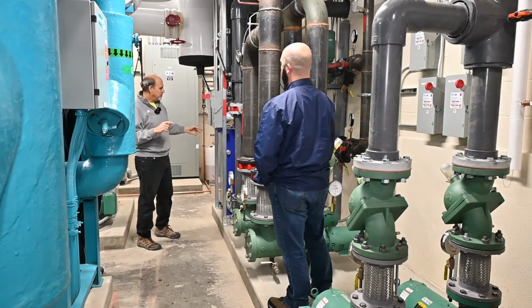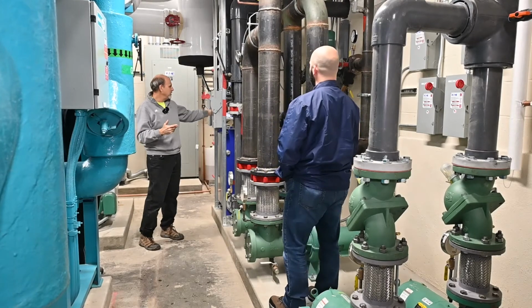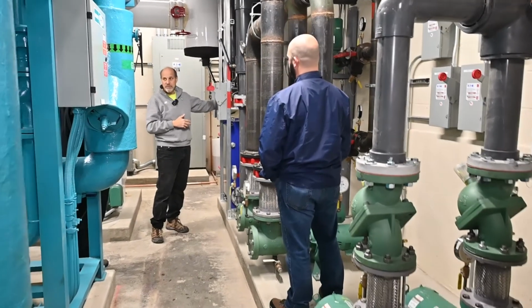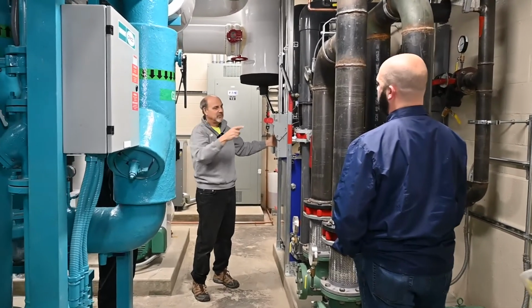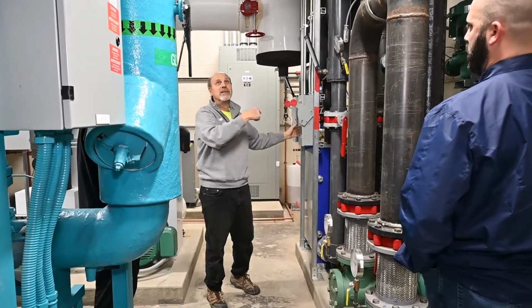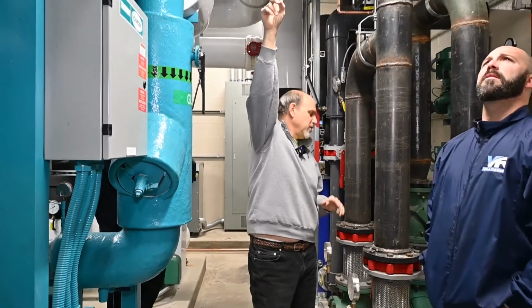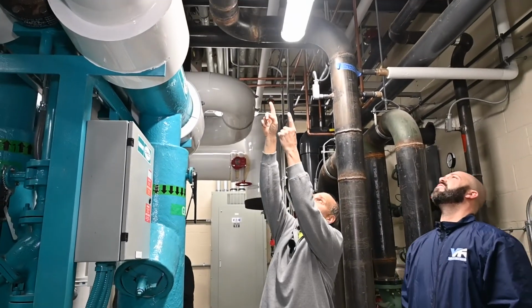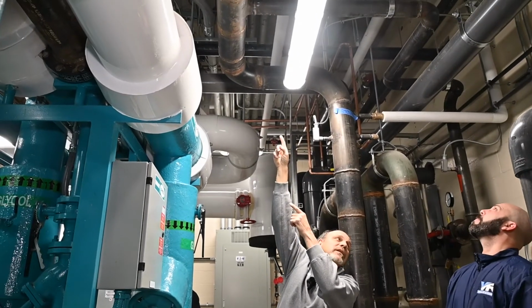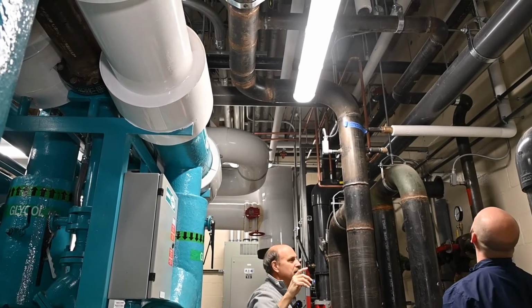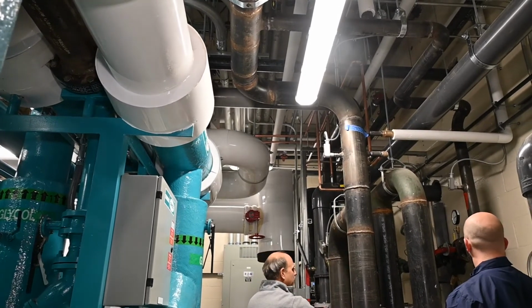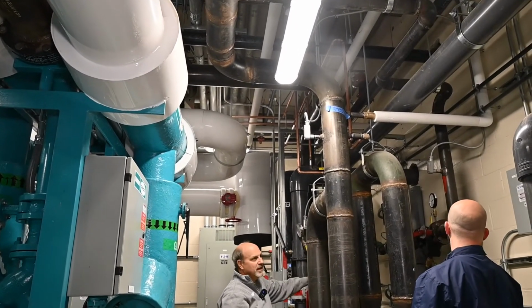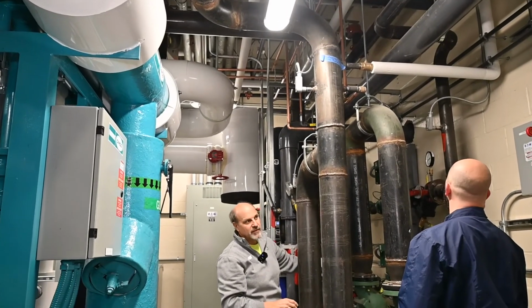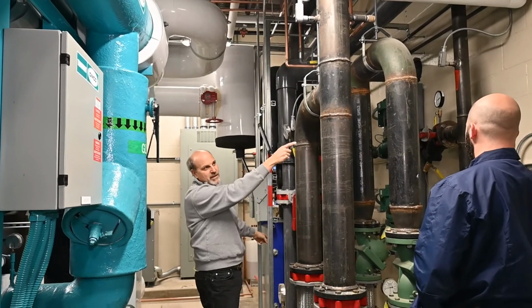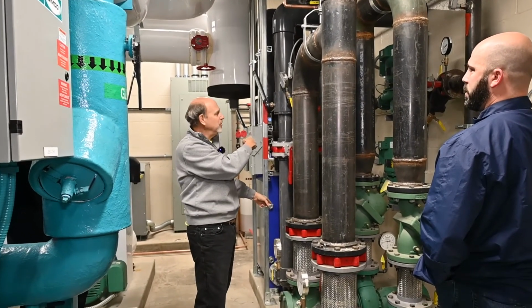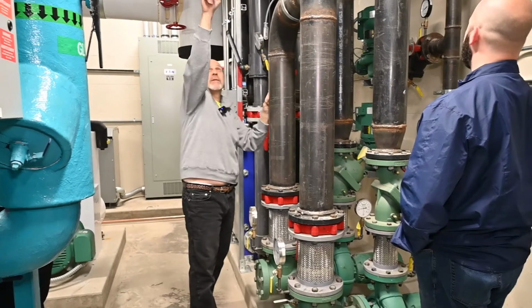The other thing that we do, as an energy-saving method, is obviously we've got to heat the warm floor with the 3-inch piping. So what we do is we capture some of that heat before it goes out to the cooling tower and use that heat for the warm floor. So if you can see right here, before it goes into these pumps here, is what we call a bridge connection right here. This 3-inch pipe and this 3-inch pipe here. We're pulling off of this loop before it goes through the heat exchanger to come over, down, through these 2 wall-mounted pumps, P8 and 9, and that's what's connected to your warm floor. So we're pulling that heat off before we reject it and waste energy on your cooling tower to dump the heat in your floor. It comes back, and then it just dumps back into the same pipe.